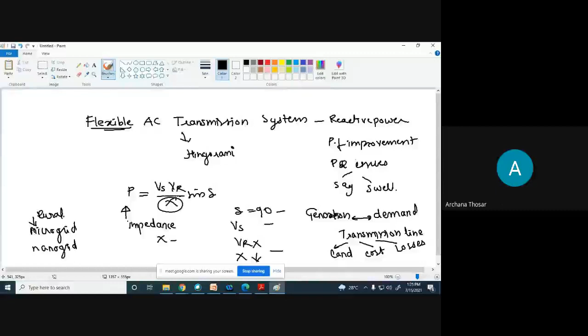So as the reactive power demand changes, a permanent installation of any reactive element on the transmission line will not solve the purpose; it may even create a problem. So what is the solution? You have to reduce this X by introducing some controller into the transmission line, by creating a situation wherein reactive power is injected into the line.